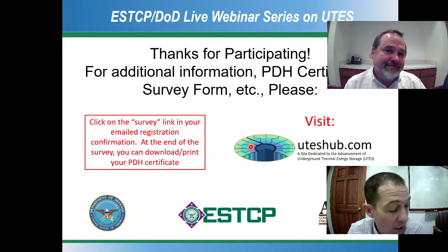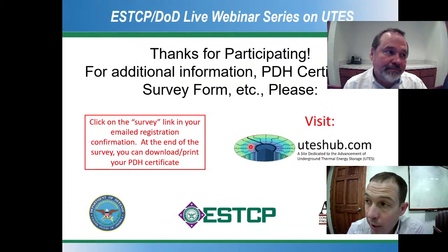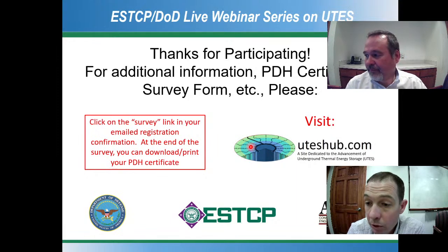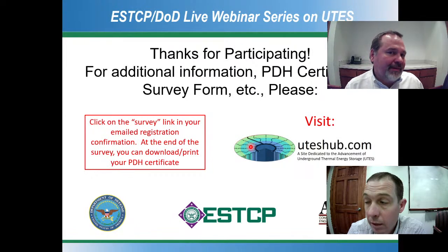We've seen issues with HDPE welding, and just the sequence of operation in general. I mean, controls. In the commissioning world, controls are our biggest problem. A lot of times, you just want to make sure that stuff gets programmed correctly and is operating right. I think Brandon may have touched on it before, I can't remember, but in general, with VFDs, from an energy standpoint, you want to drive the fan or the pump or whatever to the lowest possible speed.